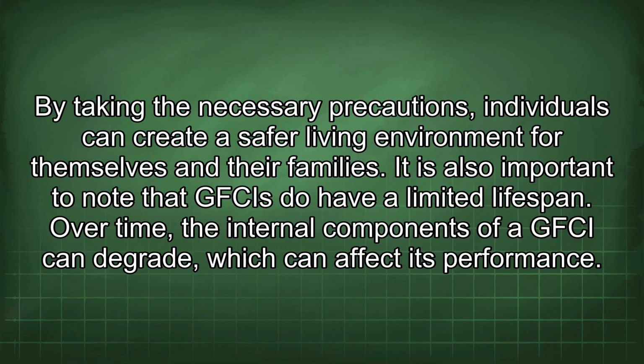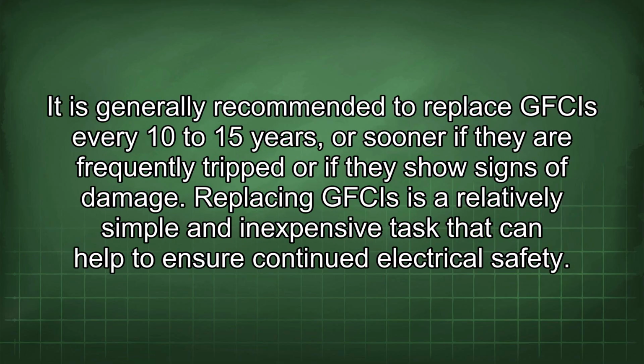It is also important to note that GFCIs do have a limited lifespan. Over time, the internal components of a GFCI can degrade, which can affect its performance. It is generally recommended to replace GFCIs every 10 to 15 years, or sooner if they are frequently tripped or if they show signs of damage. Replacing GFCIs is a relatively simple and inexpensive task that can help to ensure continued electrical safety.